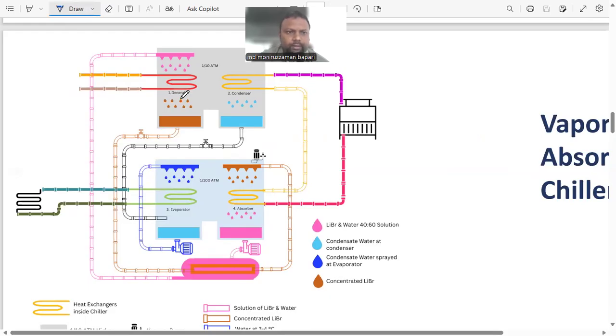Remember, in vapor absorption chiller, we have two different chambers. One chamber is at higher pressure, and the other chamber is lower pressure chamber. The chamber at the top is actually the higher pressure chamber. The pressure inside is 1/10 of atmospheric pressure. But the pressure at the lower pressure chamber is very low, 1/100th of atmospheric pressure. So these two are the chambers.